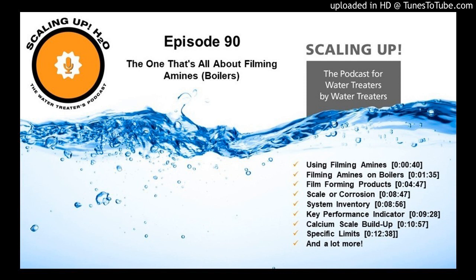So what's nice about a film forming amine product that was designed for a boiler application is that amines already inherently are higher pH molecules. So while the filming amines' impact over pH is not as great as an alkalizing amine's impact over pH, they're both inherently going to buffer to a higher pH. So that takes care of the filming amines, not only take care of your corrosion inhibitor, and then the alkalizing amines are exactly what they say they're going to do. They're going to not only neutralize pH, but then continue to drive pH up. So you're going to consume carbonic acid and just drive your pH in the system up.